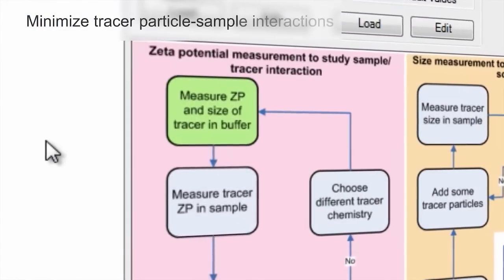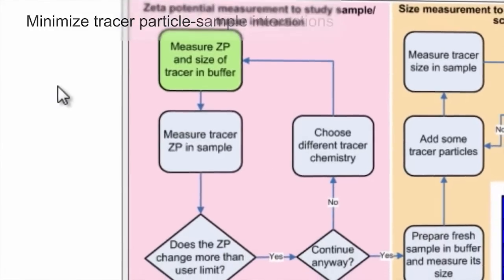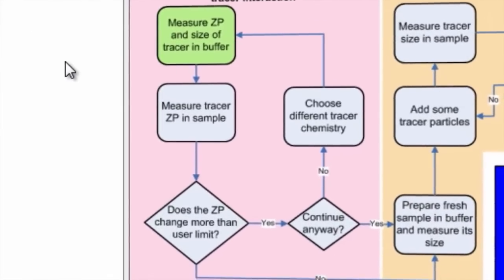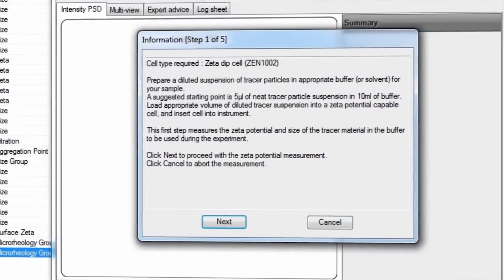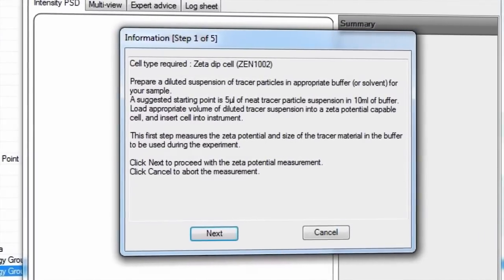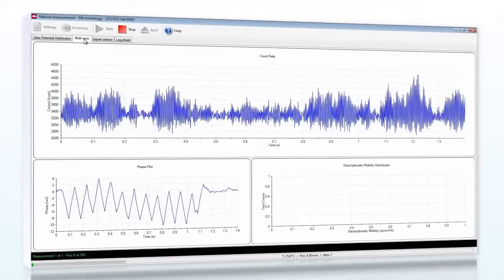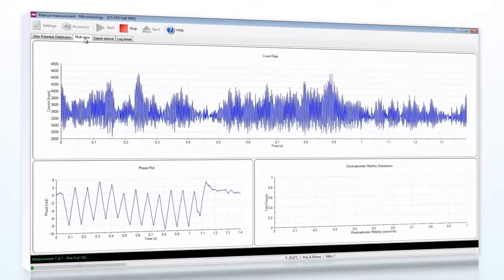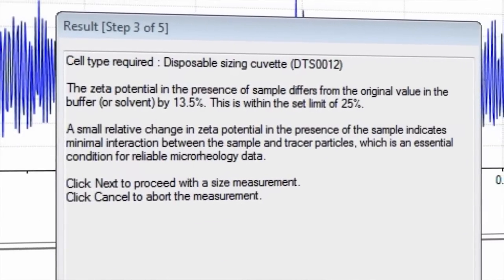An essential requirement is to minimize tracer particle to sample interactions since these will affect particle diffusivity and hence the measured mean squared displacement. This is assessed by using a zeta potential pre-measurement step and comparing the value for tracer particles in solvent alone and then in the presence of the sample. If the zeta potential change between these measurements is significantly different then the use of a different tracer particle surface chemistry may be required.